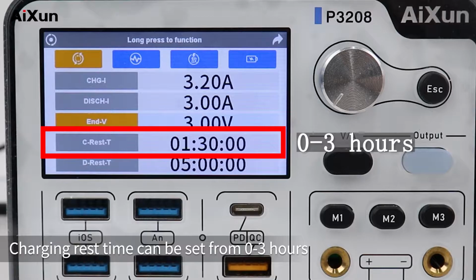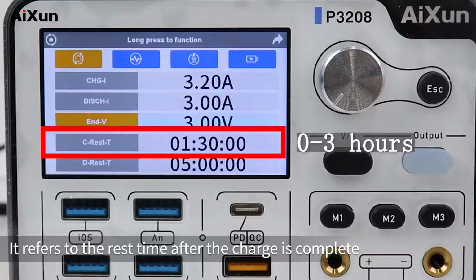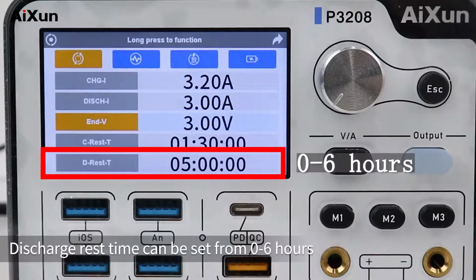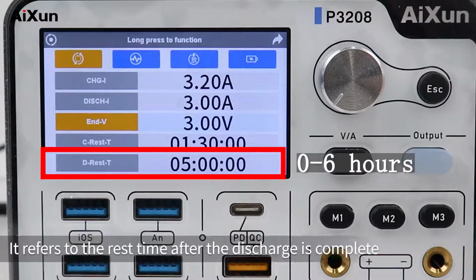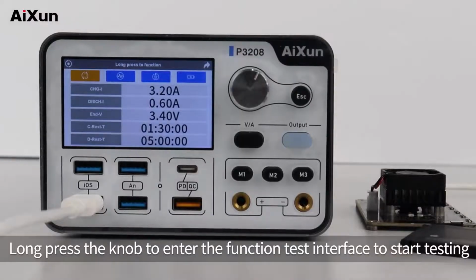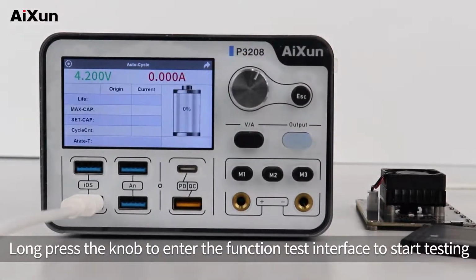Charging rest time can be set from 0 to 3 hours. It refers to the rest time after the charge is complete. Discharge rest time can be set from 0 to 6 hours. It refers to the rest time after the discharge is complete. Long press the knob to enter the function test interface to start testing.